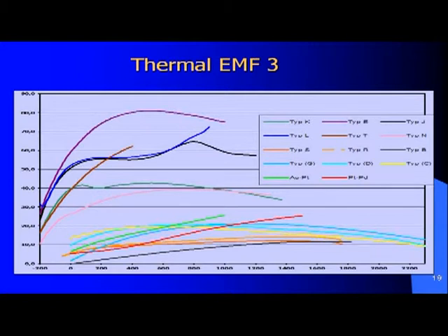And they are very good, very reliable, extremely stable, good sensitivity, but for industrial use they are not suitable. In no case. The drift rate is very low, but they are very sensitive to contamination. So outside a laboratory environment, it is nearly impossible to use them.